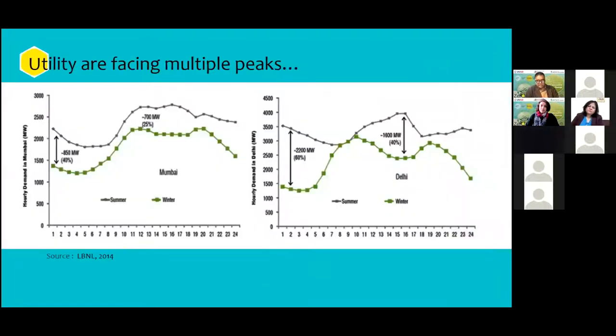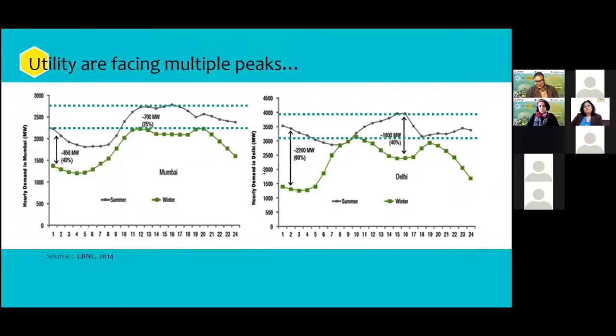So if we pause and look from a utility lens, the challenges are mainly governed around rising peak demands and the requirements of additional infrastructure to support this. In addition to the seasonal peak demands that are being experienced, we now face a scenario where you see multiple peaks within the same day. And if we truly want a resilient grid network and reduce the burden on it, the buildings need to contribute towards shaving these peaks and flattening this curve.